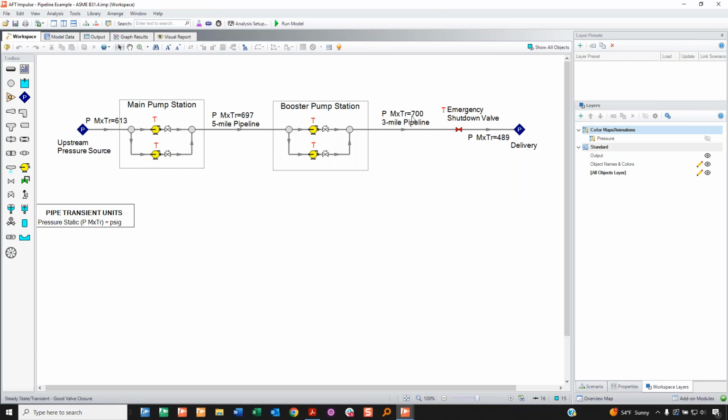So all of a sudden, I'm now meeting that code, and I can present this to a client or to whoever you're working with to say, hey, this is proof — is a hard word — but this is suggesting that closing a valve in this manner would help prevent surge and help us meet code.